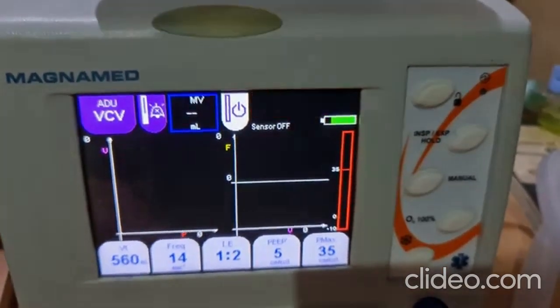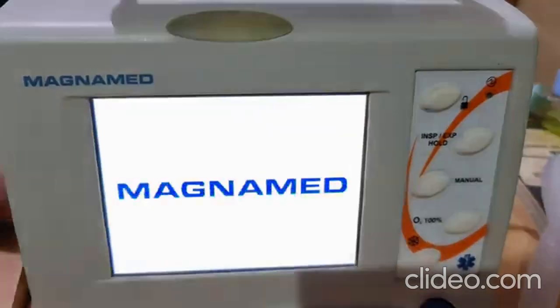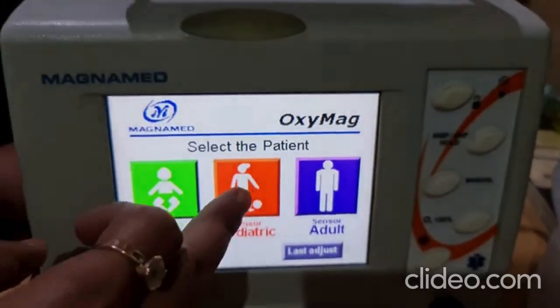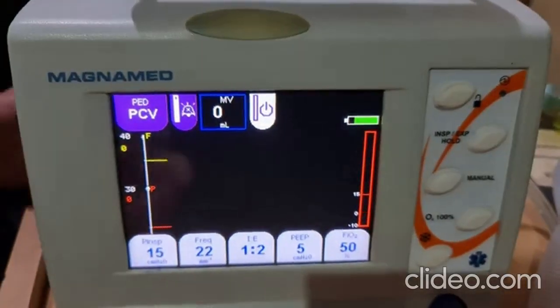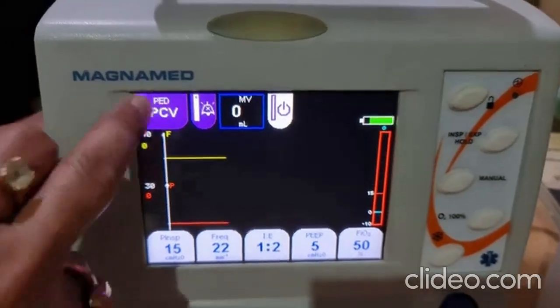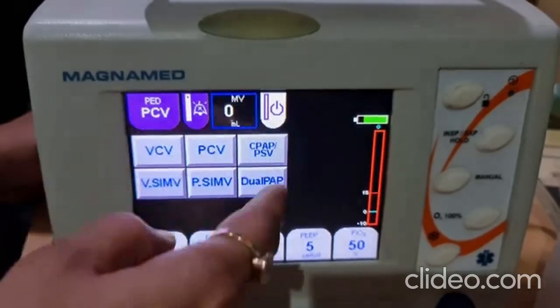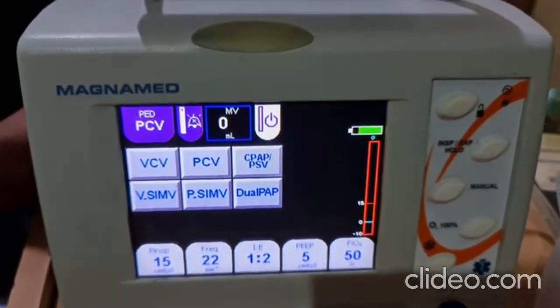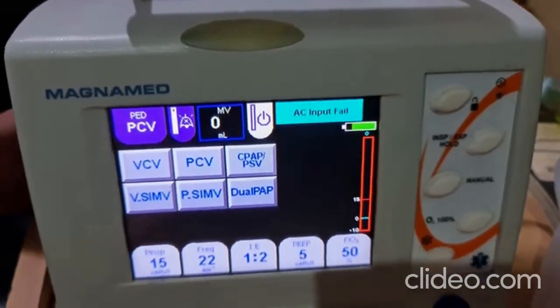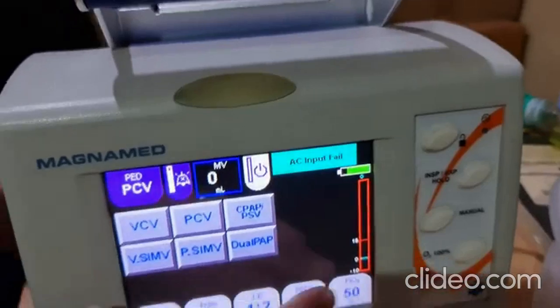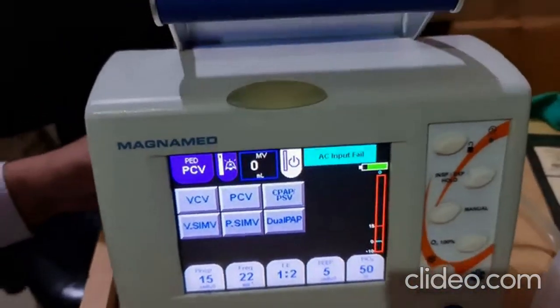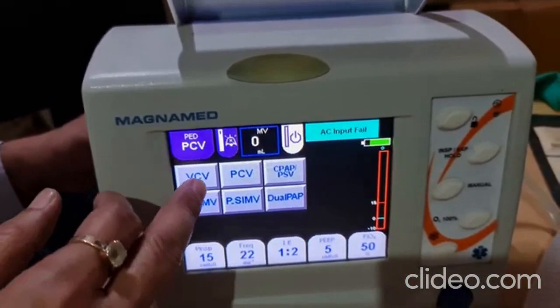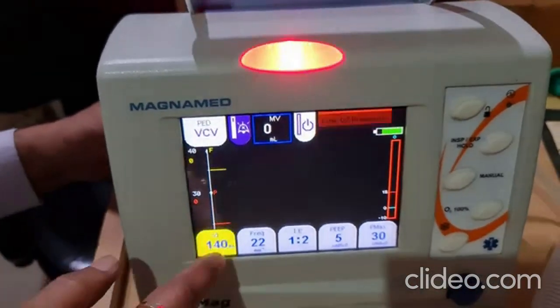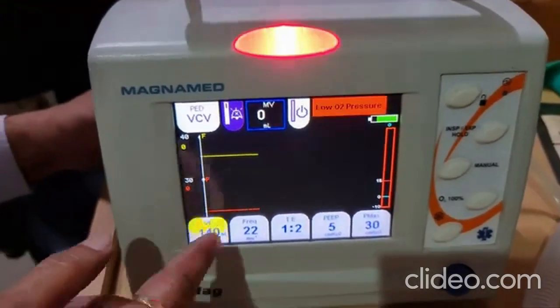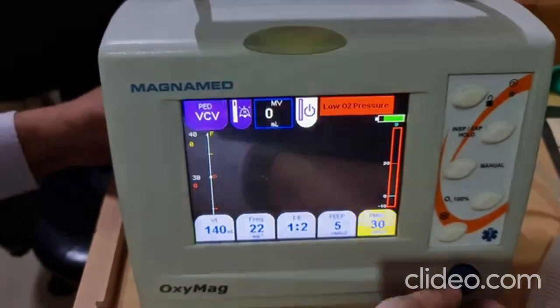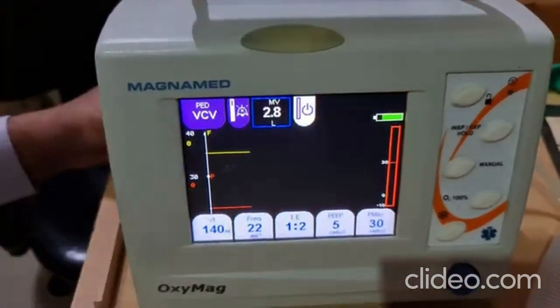This is adult mode. If you want to use pediatric, you can select pediatric. This is the pediatric mode. In pediatric, you have all the modes like adult mode, but the parameter limits differ. The default parameters will be according to the pediatric patient. If you want to change the mode, just select and confirm the blinking parameter to change the mode. Now it has come to pediatric VCV.